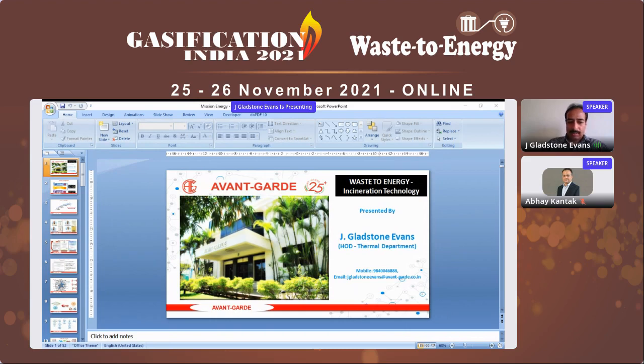Another aspect is the chlorine and the initial deformation temperature of the ash, because at a lower temperature itself the ash will melt. Whereas if you see Indian coal, bagasse or rice husk, these temperatures are more than 1000 degrees, whereas here it is around 700 or 800 degrees centigrade.